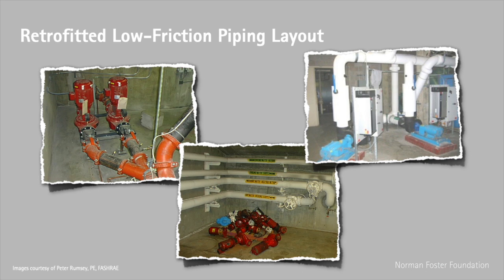Repiping another pumping loop, then adding variable speed drive, doubled the flow and saved 85% of the energy. So Peter simply asked the pipe fitters to lay out those supply pipes as if they were drains.